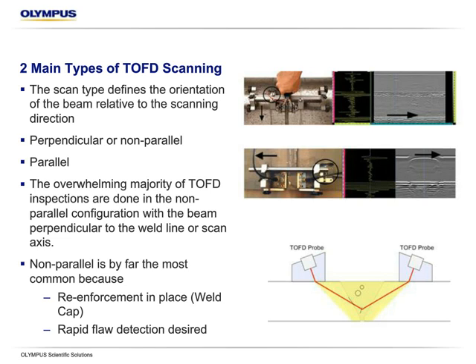The other type is the parallel. We can see here the encoder has been switched to the same direction as the beam, and you're actually rastering across the weld or component. Now this obviously has a limitation: any weld reinforcement in place is not going to allow this to happen. So in a lot of cases we'll do a perpendicular scan, get a diagnosis, and then maybe a small amount of reinforcement may be removed to get a parallel scan. A parallel scan will give more accurate sizing capabilities, especially in the height plane, and it will also position the flaw very accurately as well, but it usually has that limitation.